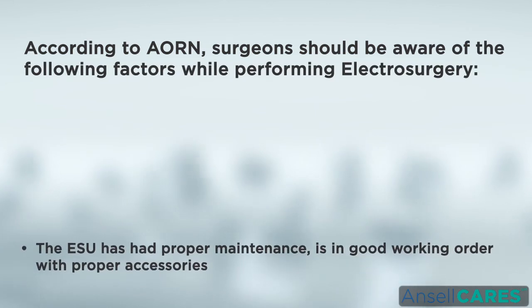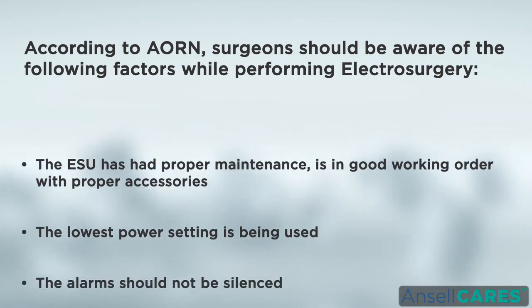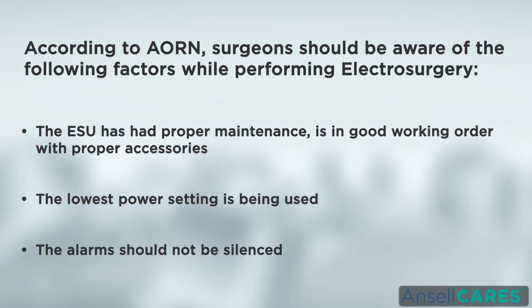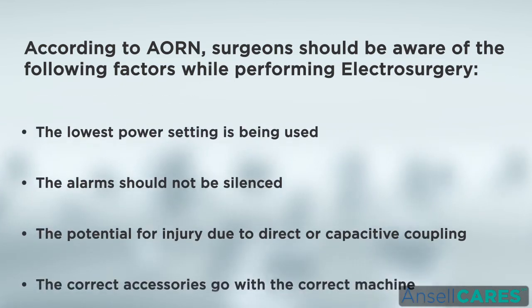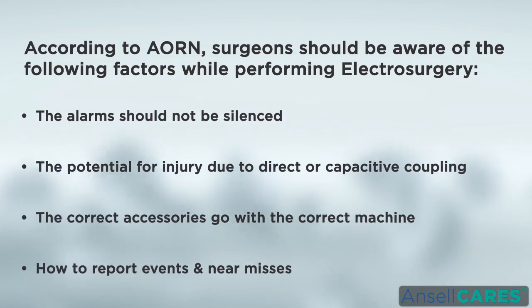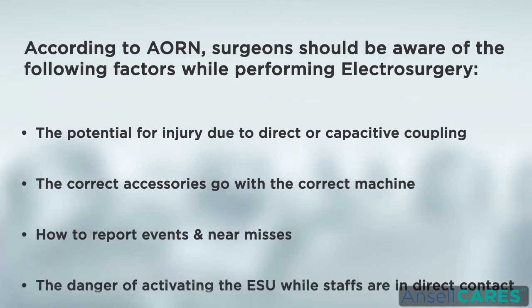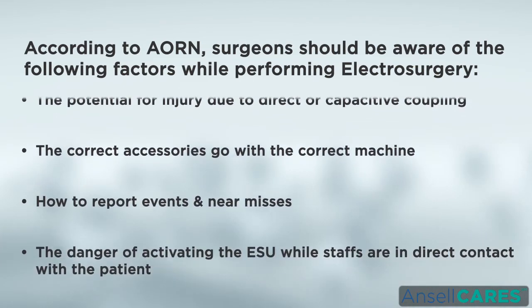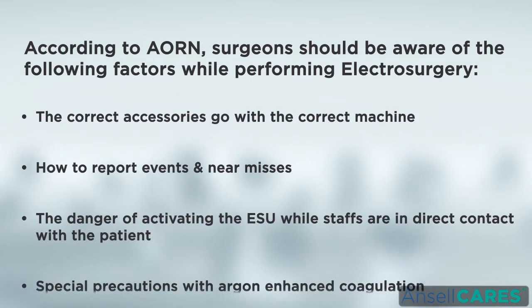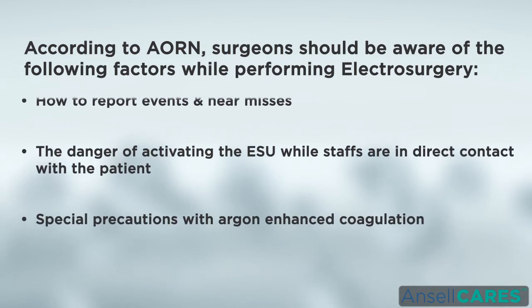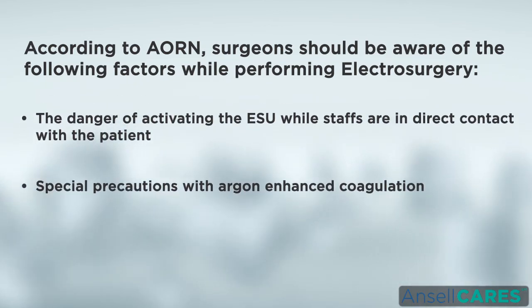According to AORN, surgeons should also be aware of the following: that the ESU has had proper maintenance and is in good working order with proper accessories; that the lowest power setting is being used; that alarms should not be silenced; the potential for injury due to direct or capacitive coupling; that the correct accessories go with the correct machine; how to report events and near misses; and the danger of activating the ESU while staff are in direct contact with the patient. Special precautions should be taken with argon-enhanced coagulation.